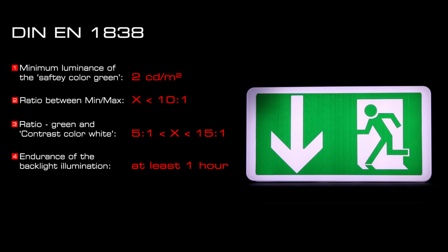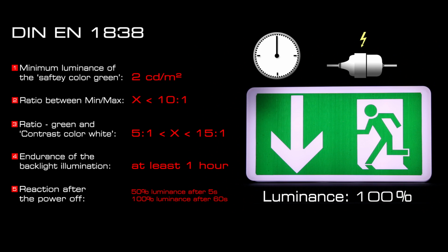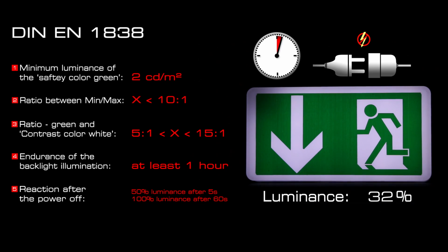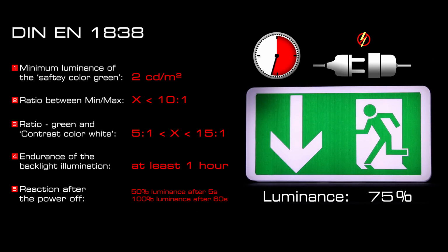The safety sign must reach a minimum of 50% required luminance within 5 seconds and 100% required luminance within 60 seconds of time.